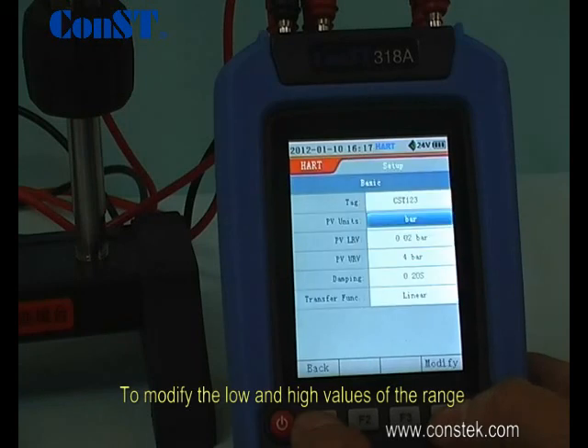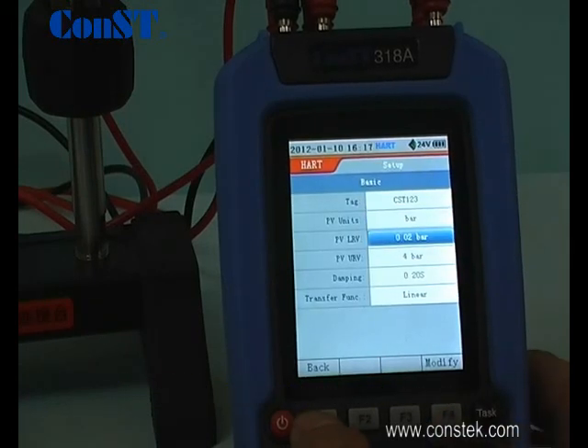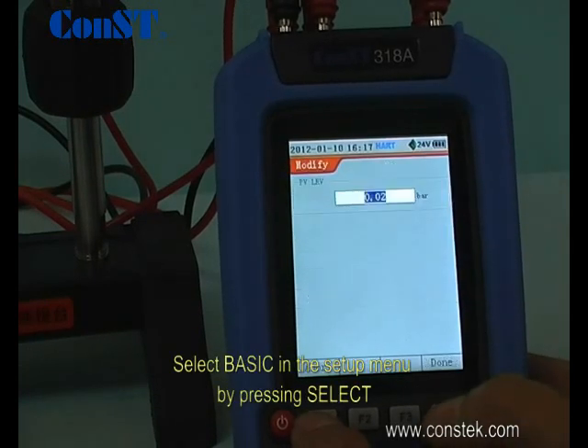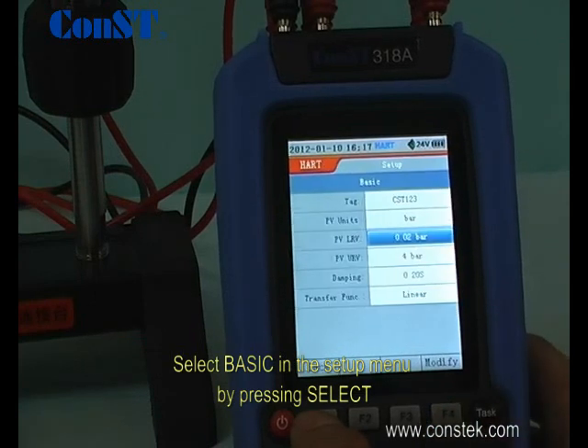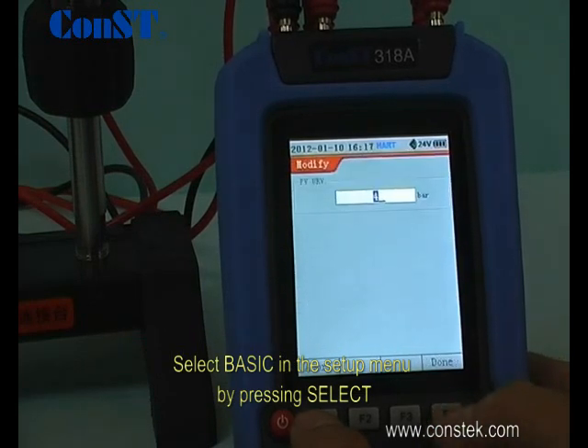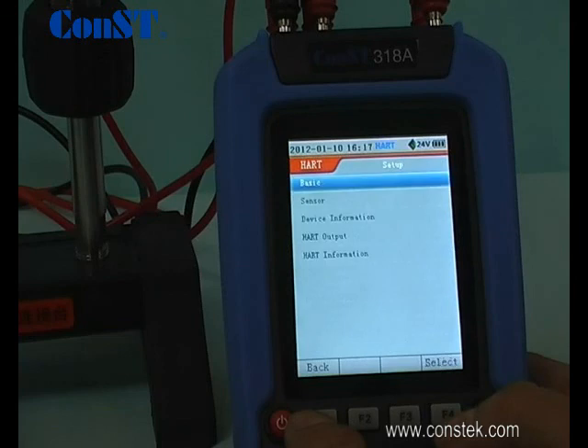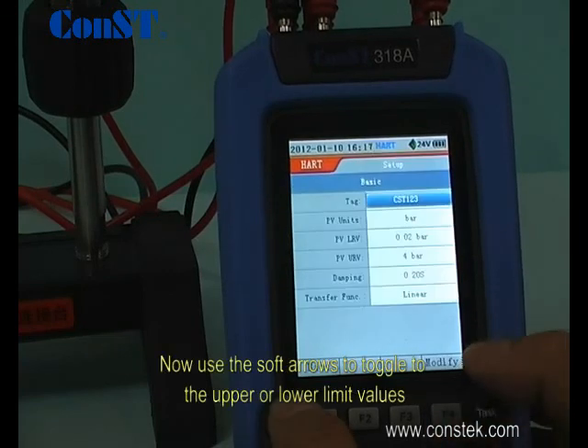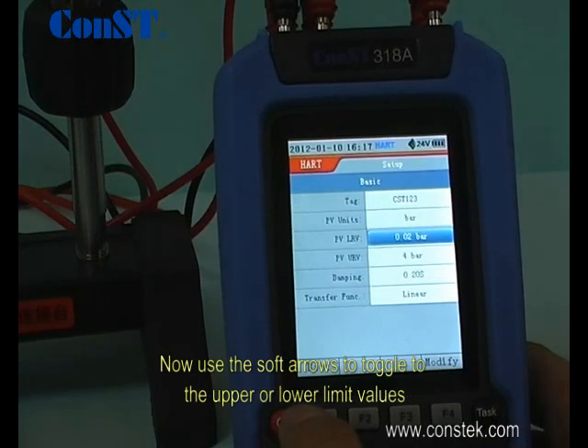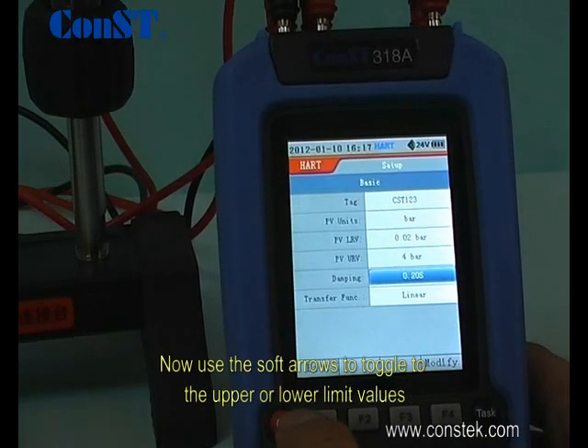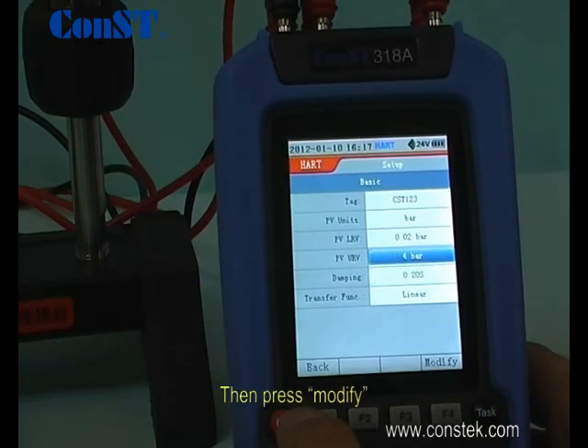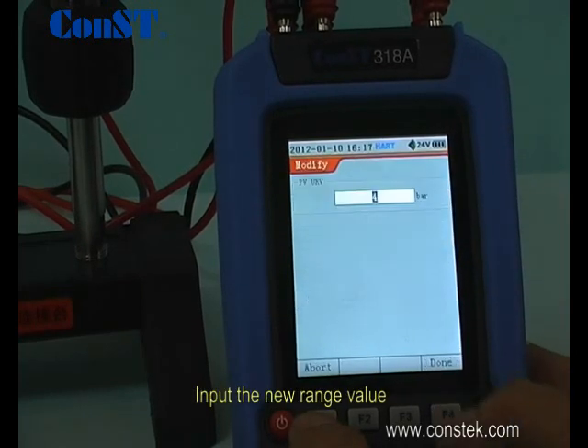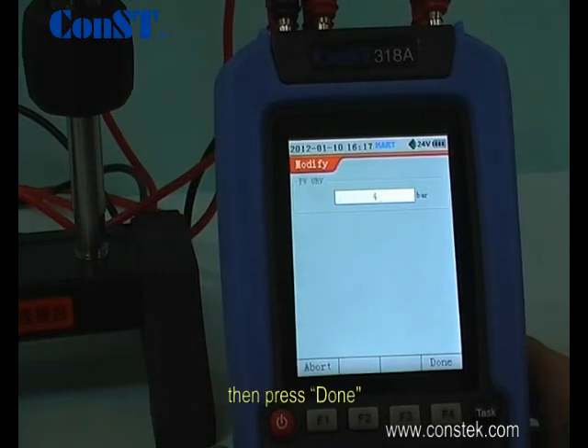To modify the low and high values of the range, select Basic in the Setup menu by pressing Select. Now use the soft arrows to toggle to the upper or lower limit values. Then press Modify. Input the new range value, then press Done.